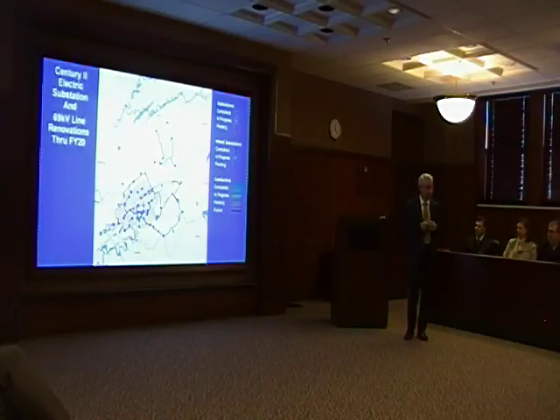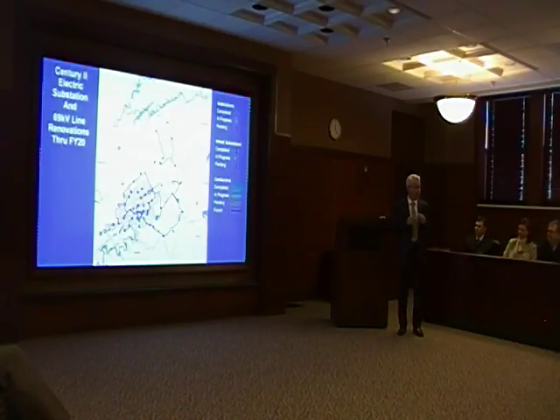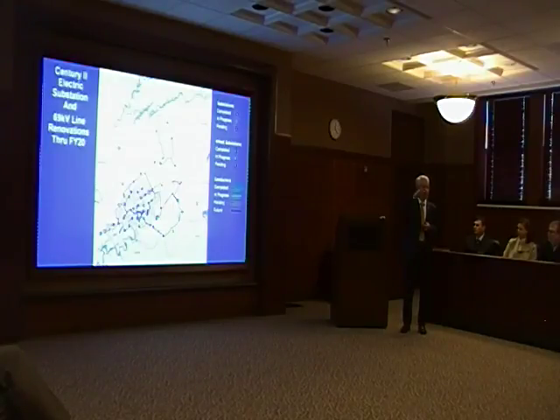Told you I had another little map back here. I wanted to point out a few things about how we work on substations and how that affects how we move power about the system. Now, the lines here are multicolored, but these conductors are the 69 kV system that interconnects the substations, so we have a loop system. If you remember, a couple of months ago we talked about the gas system and the advantages of the new loop pipe system with the South Loop addition. We have that same feature on the electric side, where we have the ability to move power in different directions around these loops.